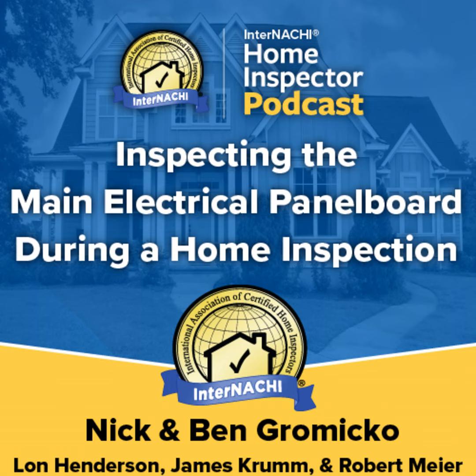Main bonding jumper, or MBJ. At the main service panel board, the two ungrounded or hot service conductors from the meter base attach to lugs or terminals at the main breaker. The incoming grounded neutral service conductor attaches to the main lug of the neutral bus bar. In a typical electric service panel board, the neutral bus bars are bonded to the service panel board enclosure by means of a special bonding screw or strap provided by the equipment manufacturer. That component is called the main bonding jumper, or MBJ.